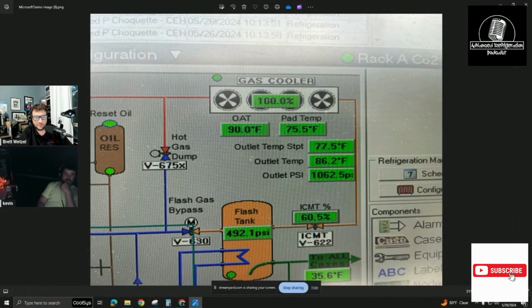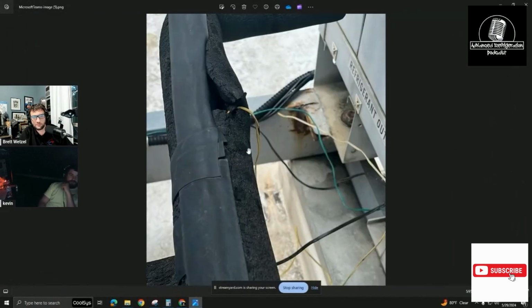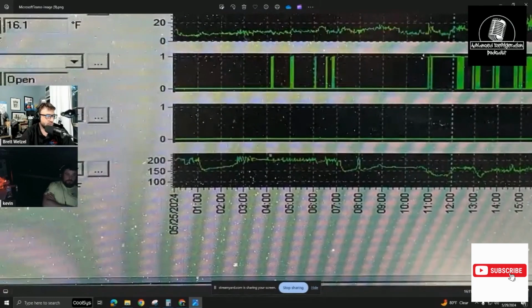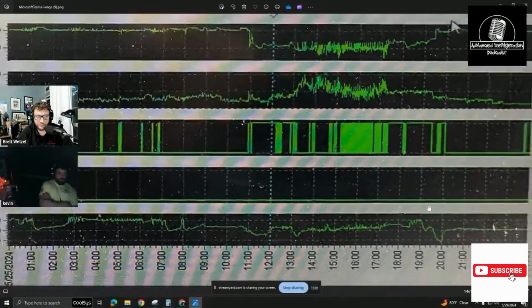See, I don't really think those hot gas solenoids even do much in those racks, but when you lose that freezer load, done. Like, especially if you have any, I think that makes sense though, because you're getting that additional superheat from that compressor. Oh yeah, yeah. When it shuts off, those racks struggle big time. Most of the time, what I've been finding, especially in an Aldi, is if I'm having superheat issues, I just scroll through the XMs, look through for P6s, because a certain manufacturer had a run of bad sensors, and every store you'll find one or two suction temp sensors reading like 100 degrees.